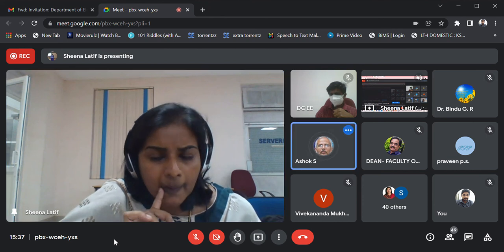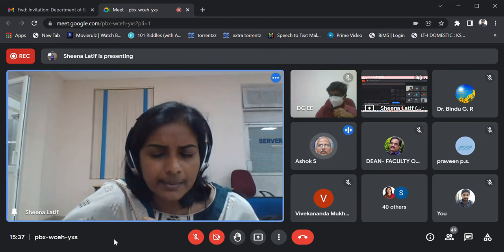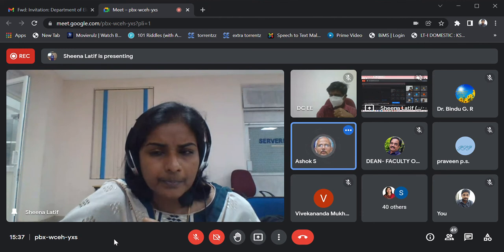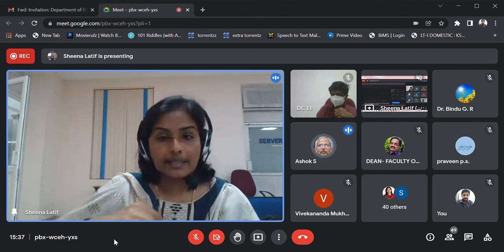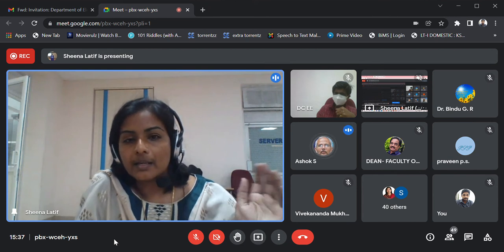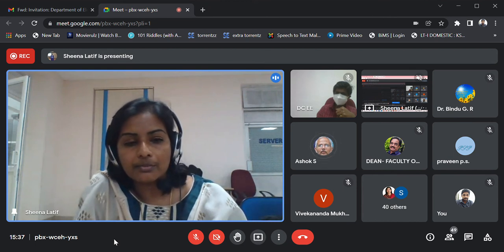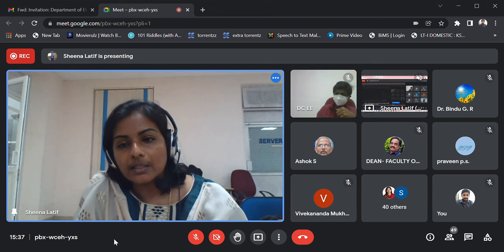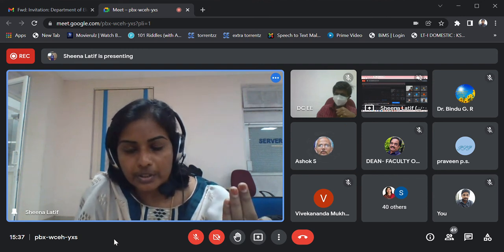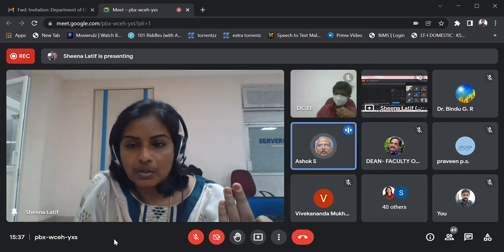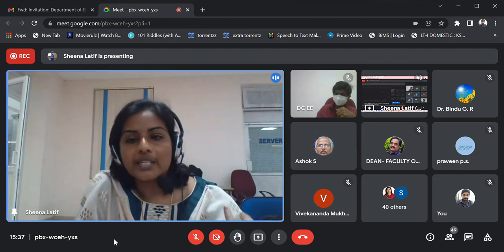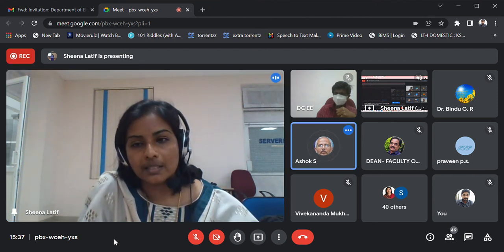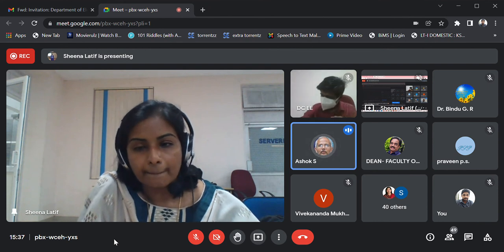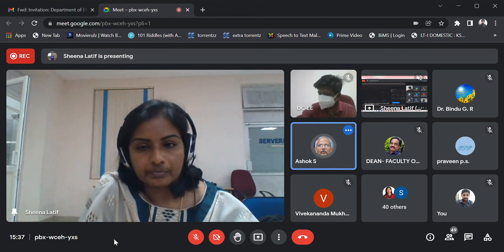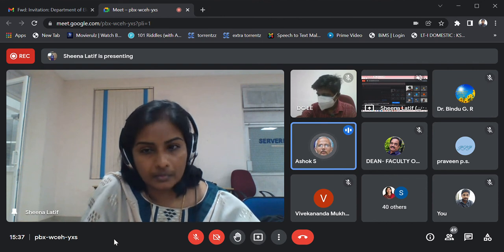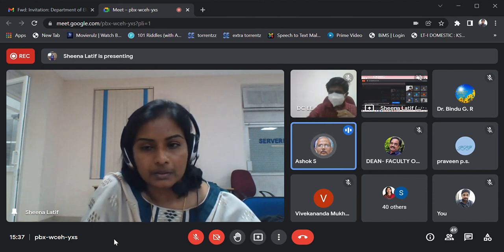My question is, is there any impact on the location? Yes, sir. There is impact. If your location, the fault impedance, and the type of fault, these three parameters are very important. The type of fault has come in your presentation. Yes. Location I have not specifically mentioned, sir. At least something should be there about that location, because it also depends on the location of the fault. Everybody knows that.